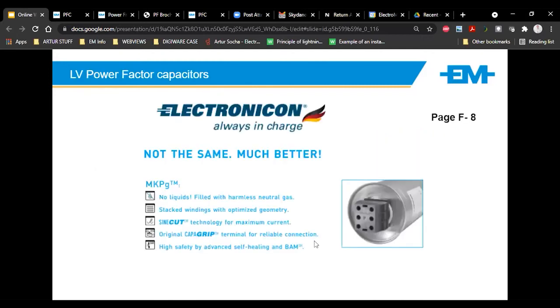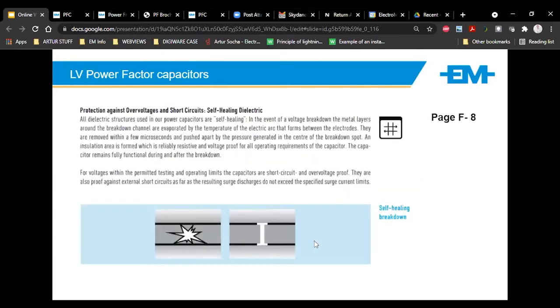We only use electronicon capacitors in our systems. They do not have any liquids. They have a harmless neutral gas, which is nitrogen. High safety, self-healing with a safety release. What is self-healing? It's just to do with the dielectrics inside it. As little transients occur in the cap, the material inside closes off after the little short circuit has occurred.